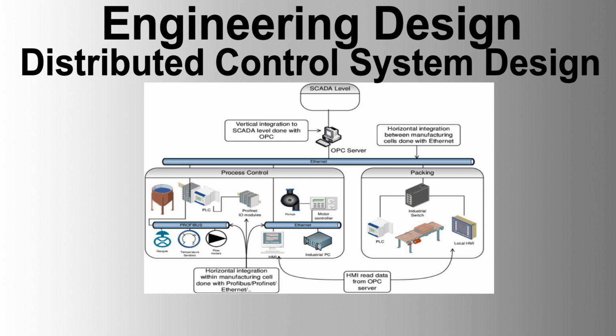3. Communication bus interface. The new DCS must be compatible with and integrated into the existing dual redundant data highway. The new operator station must be compatible with the existing network system. Communication buses must have redundant cables routed in separate paths to avoid simultaneous failure, with automatic switchover without operator intervention. The DCS must monitor the operation of all communication buses and generate system alarm messages for bus failures. Failure of both communication bus cables must not disable the DCS control modules.